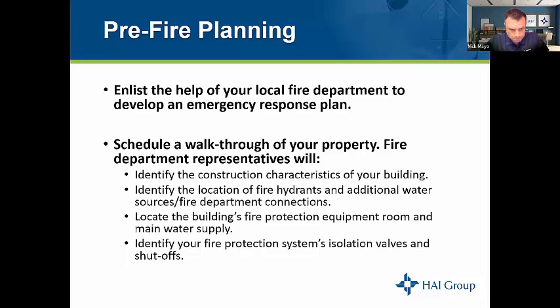Within that walkthrough, the fire department can identify your fire protection system's isolation valves and shutoffs. So along with your main control valves that come off that first branch of your sprinkler system, as we go from floor to floor within that building, identifying isolation valves and marking them with a placard is a good thing to have. Because if there's a fire, let's say on the fourth floor of a building, and you have an activated sprinkler head, we can shut down that fourth floor valve and still keep the rest of the building in service. If we close the main valve for the whole system, then the entire system could be out of service.